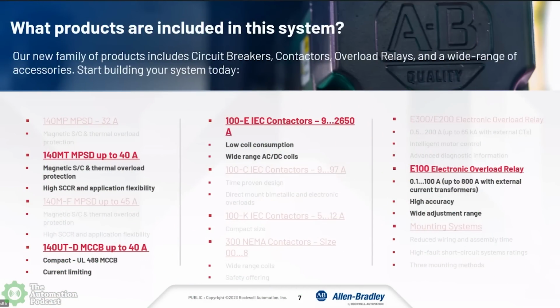So you can see on the left there, we've got our 140 MT and 140 UT. These deliver typically in a system a branch circuit protection. One advantage of our 140 MT is it actually has overload protection offered internal to the device, so you need this in conjunction with a contactor for what's called a two component starter. The 140 UT is a really compact traditional molded case circuit breaker, delivers really high short circuit current ratings and can actually be used not even in a motor application.